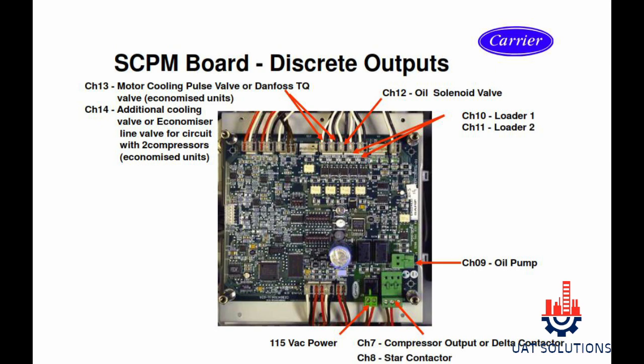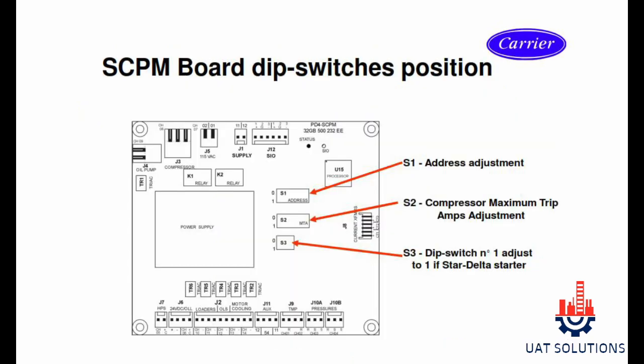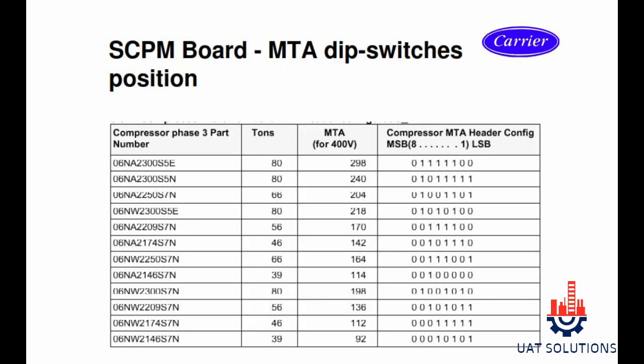The board is powered by 115 volt AC. DIP switches and their function on the SCPM board: S1 switch is used for addressing of the SCPM board, S2 is used for compressor maximum trip ampere setting, and S3 is used for compressor starter type selection. The positions of DIP switch S2 are shown, which is used to set the compressor must-trip ampere. In the table, MTA values and switch positions are shown as per the compressor models.